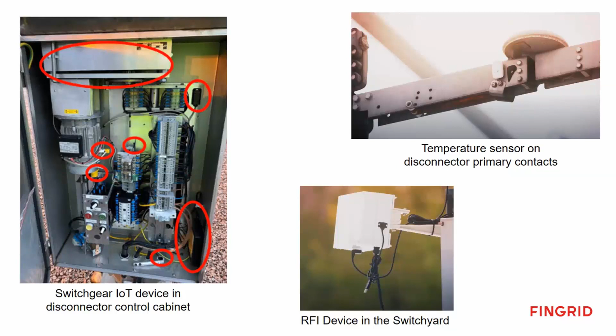All right, and one key feature of the whole Internet of Things concept is that it's fully separated from the control and protection system of the substation. Here we have the substation on the right, and below this dashed line we have the traditional conventional data environment of the substation, the automation system that is very robust and critical for the control and protection of the substation. So that's not something that we want to touch too much.